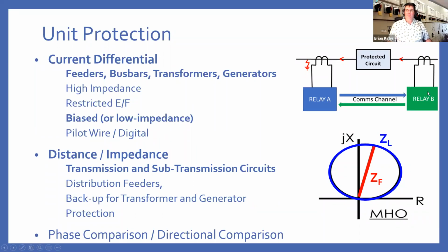Today, we very much rely on communications, and we tend to use what's called biased or low impedance schemes because it gives you the most flexibility in terms of how you connect to your current transformers. High impedance and restricted earth fault schemes may still exist in some parts of legacy schemes, but they're not widely used today. These have much tighter constraints on your current transformers, which is why they're generally not used.